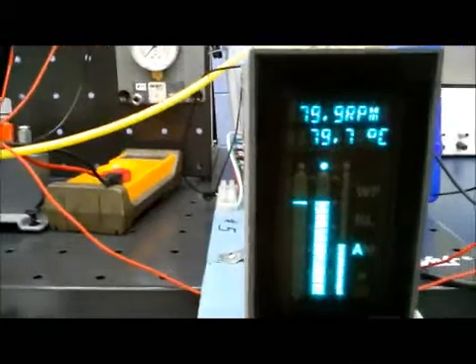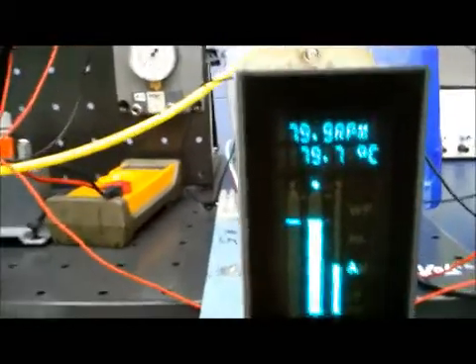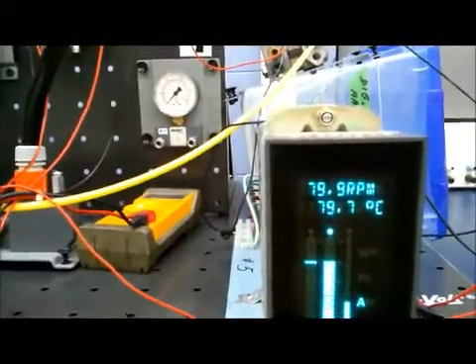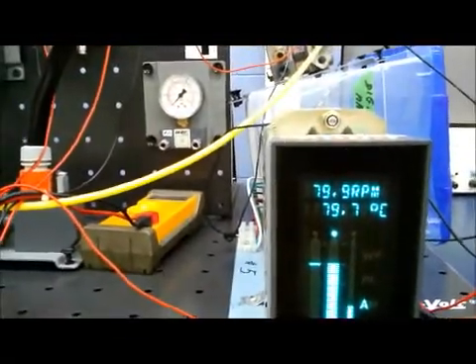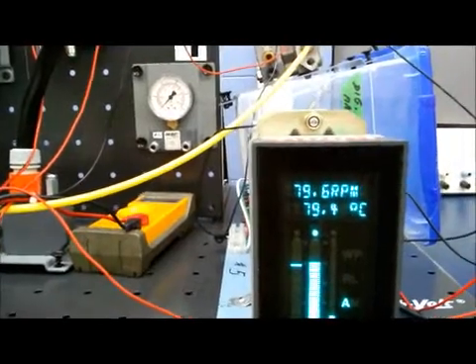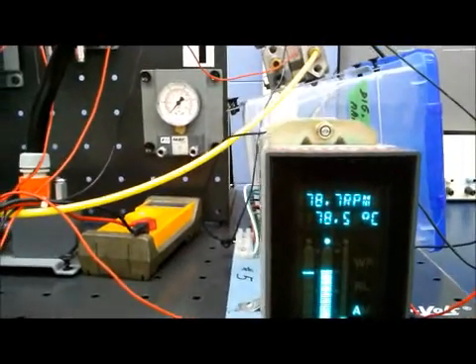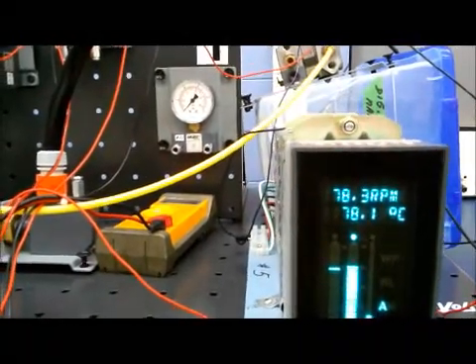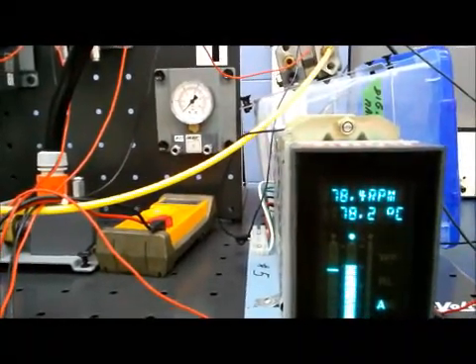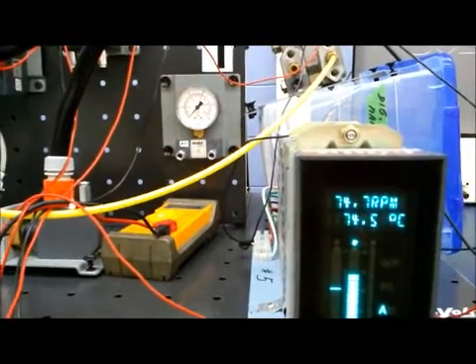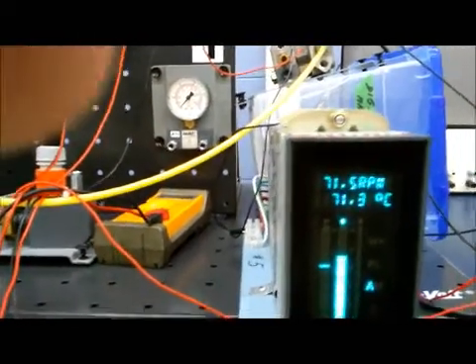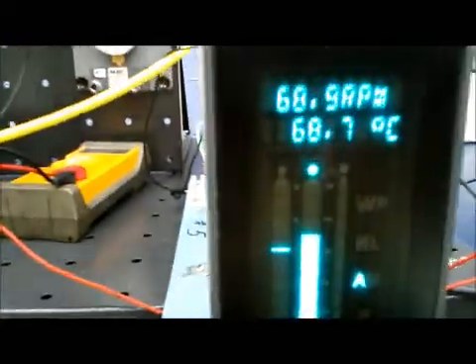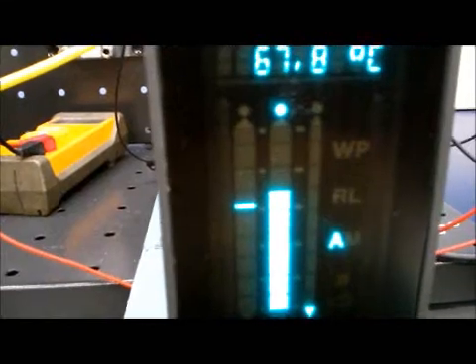So, let's make a step change in level and see how it performs. I think it changed by 20%. Oh wow, it seems very sensitive. There's 20%. And you'll see the center bar, down comes the level.